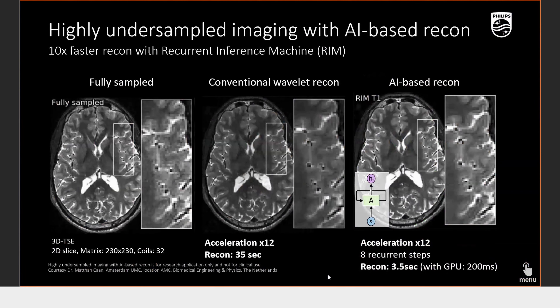Coming over to undersampled imaging with AI — all major vendors including Siemens, GE, and Philips are using compressed sense imaging. Compressed SENSE heavily undersamples your data, then reconstructs and removes all the noise to produce a smooth diagnostic image. AI has been employed here further to remove noise so that you can severely undersample data to achieve a very short scan time image.